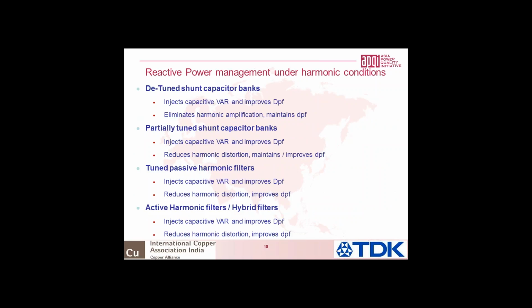As we have seen, the first solution that comes to my mind, which is very simple, elegant, and cost-effective, is detuned shunt capacitor banks. When you have a detuned shunt capacitor bank, it injects VAR and improves displacement power factor. It eliminates harmonic amplification, which means it maintains the distortion power factor. It will not improve the distortion power factor, but it will not make it worse. Then you have the partially tuned shunt capacitor banks, which inject capacitive VAR and definitely improve displacement power factor. But being partially tuned, they can also either reduce or maintain the distortion power factor.